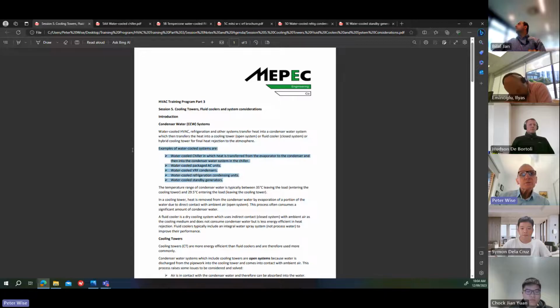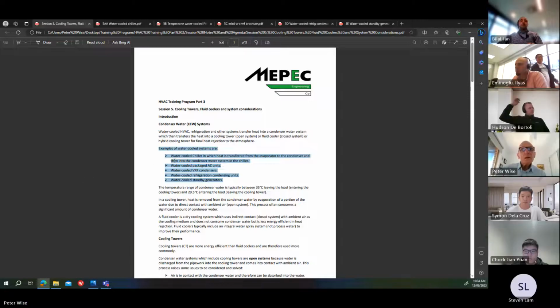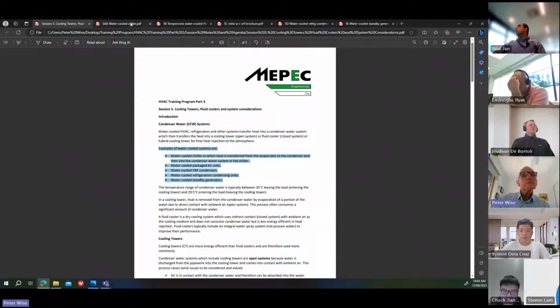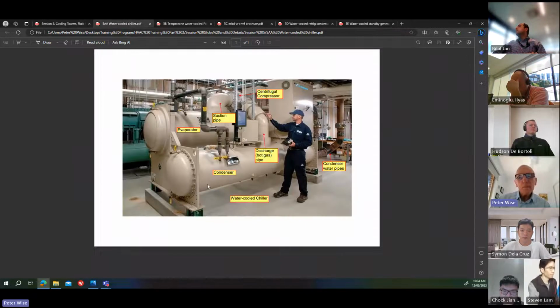Some examples of water-cooled systems that you're likely to encounter at some point in your work. A water-cooled chiller, where heat is transferred from the evaporator to the condenser and then into the condenser water system in the chiller. So here's a water-cooled chiller.